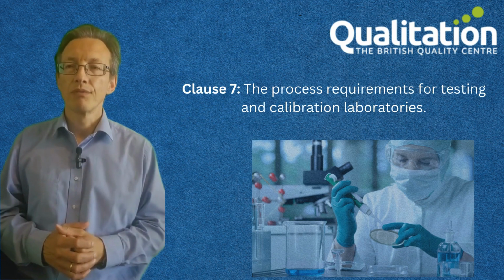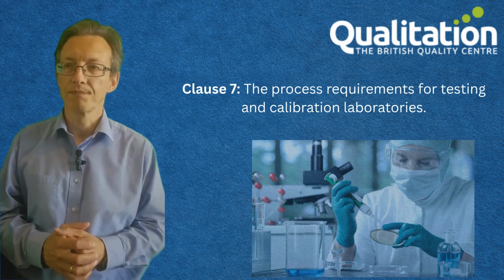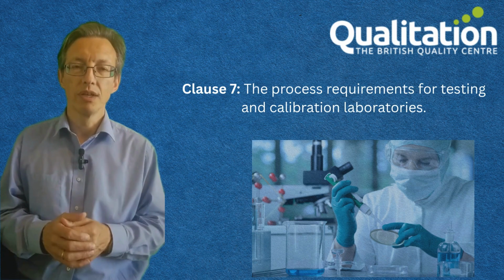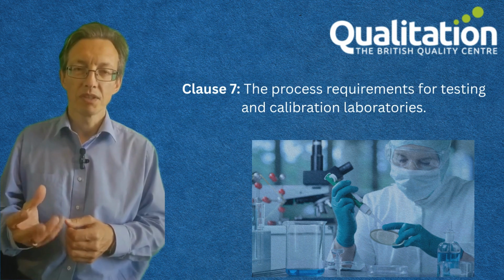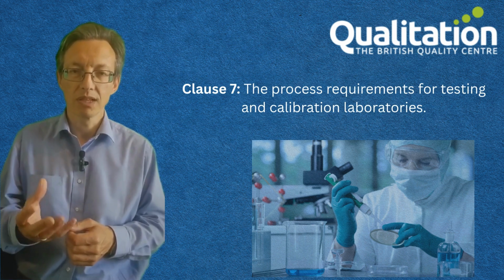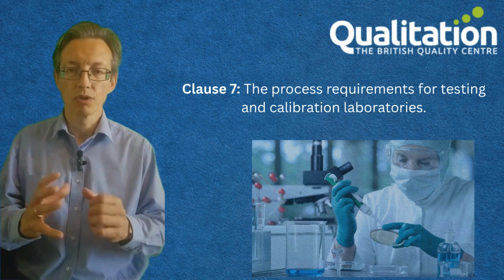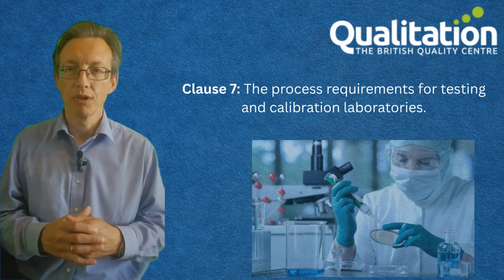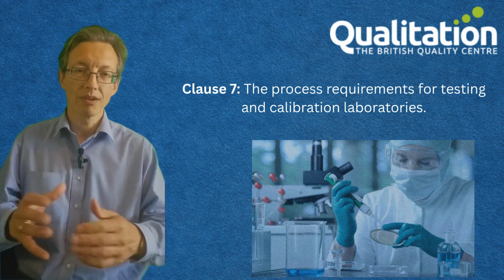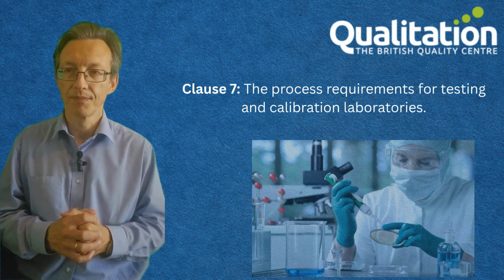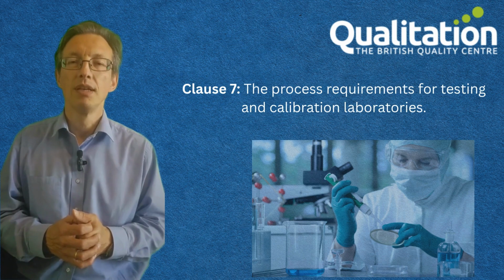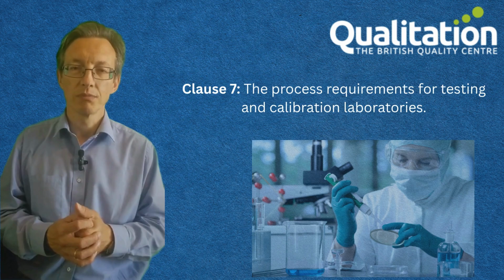Then we get to clause 7.4, handling of test or calibration items. Items must be managed to prevent contamination or mix-ups. So what we're referring to here is when you have a sample, you mustn't be handling it bare-handed, you must use gloves, it must be in an air-controlled scenario, and other contaminants must not be allowed to become involved, nor must the surrounding environment interact with it inappropriately. The consultant's approach, therefore, is to implement clear labeling and storage protocols. Without that, you've no idea which sample is which and where or how it was prepared.